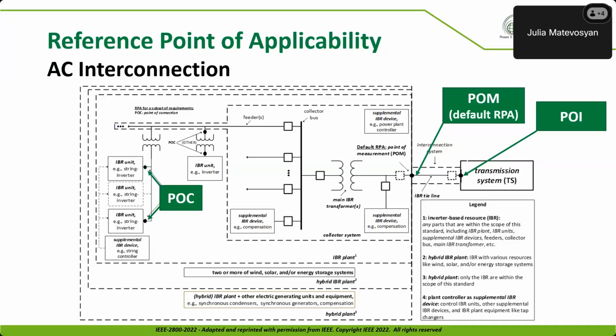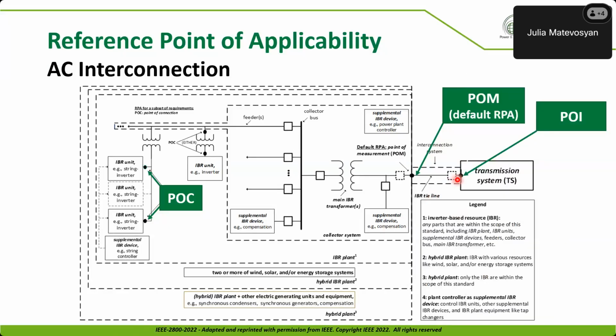Before we get into the details, I'm going to mention interconnection system a little bit during the next 10-15 minutes. And I thought it would be great to make sure we are all on the same page. So the standard defines interconnection system. I'm showing that on my screen here with the red pointer as the tie line between the point of measurement and point of interconnection. So IBR tie line or interconnection system are the same thing. So we'll talk about interconnection system protection a little bit. So I want to make sure that we are on the same grounds as to what is the meaning of interconnection system.